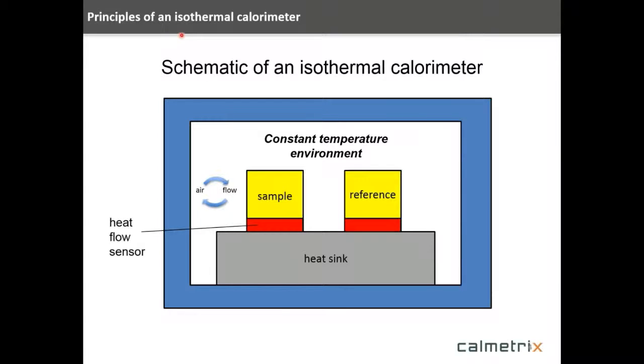Let's talk about the basic principles of an isothermal calorimeter. Here you see a schematic. Starting on the inside, we have the sample and the reference. The sample sits inside a 125-milliliter sample cup — these are reusable. We run that against a reference material, typically a metal that has no reaction during the experiment. This is a differential technique to improve baseline noise. Both the sample and reference sit on top of heat flow sensors, which are thermoelectric devices, and they connect to a heat sink — in this case, a large aluminum mass.